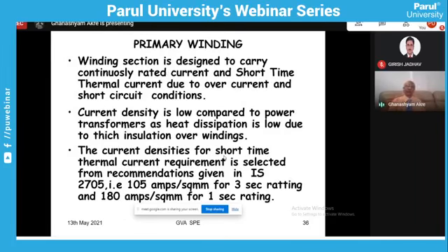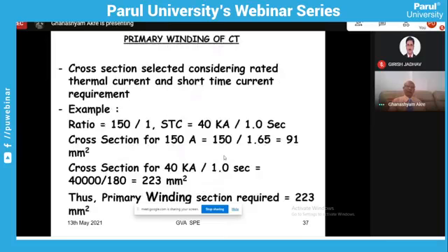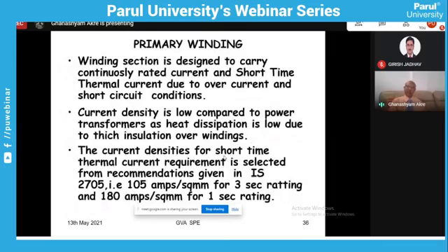You can see the primary winding. Here it can be a bar primary, it can be a hairpin type as I showed you, or it can be a live tank which has a wound primary. But the selection of the primary is also very important here, because in the instrument transformer, the primary has to carry the operating current but also has to carry the short circuit current.